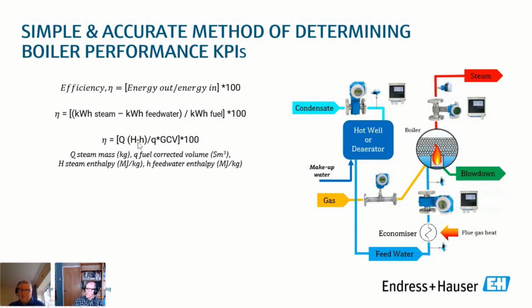They're looking at the difference in the specific enthalpy. So this is the heat content of the steam at wherever pressure this is from steam tables, and the feed water specific enthalpy at this temperature here, wherever it is in steam tables again. And again, we're just dividing that by the corrected volume times the calorific value. It's a couple of percent out because you're not taking into account what's happened with blowdown. And blowdown itself is obviously just what's going in less what's coming out. The difference we're associating with what's been blown down.